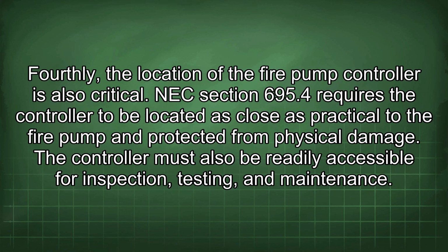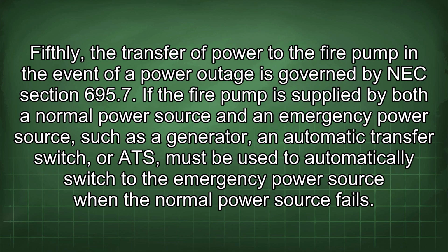Fourthly, the location of the fire pump controller is also critical. NEC Section 695.4 requires the controller to be located as close as practical to the fire pump and protected from physical damage. The controller must also be readily accessible for inspection, testing, and maintenance. Fifthly, the transfer of power to the fire pump in the event of a power outage is governed by NEC Section 695.7. If the fire pump is supplied by both a normal power source and an emergency power source, such as a generator, an automatic transfer switch, or ATS, must be used to automatically switch to the emergency power source when the normal power source fails.